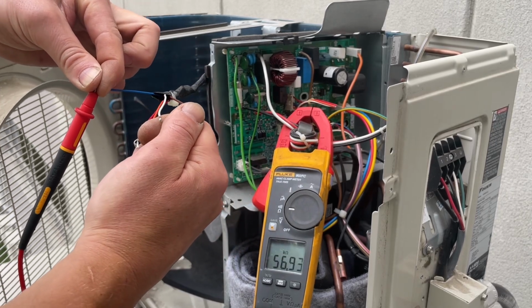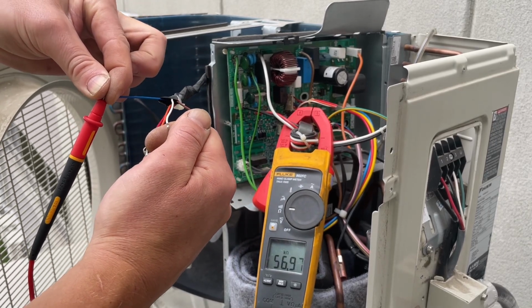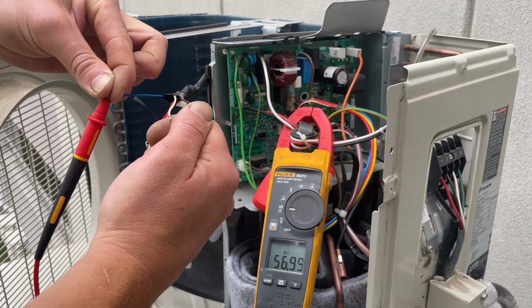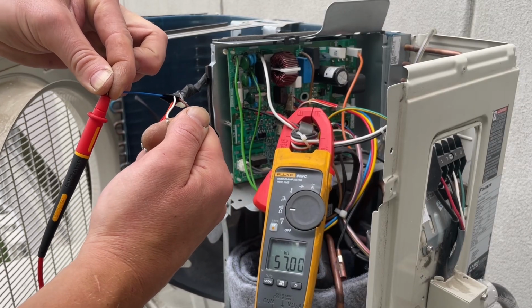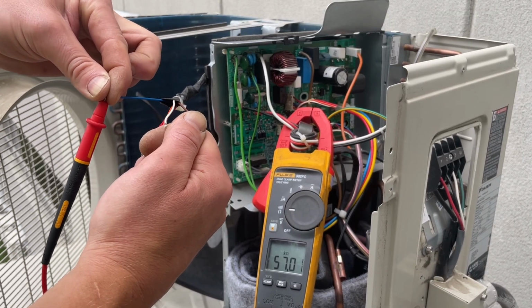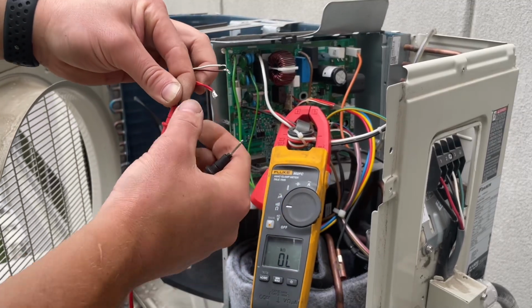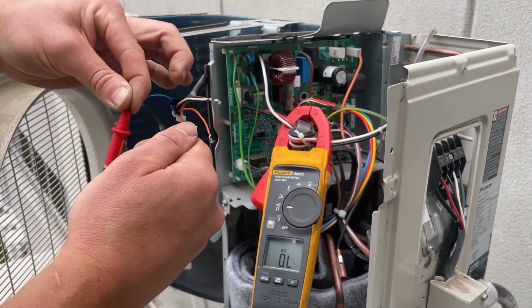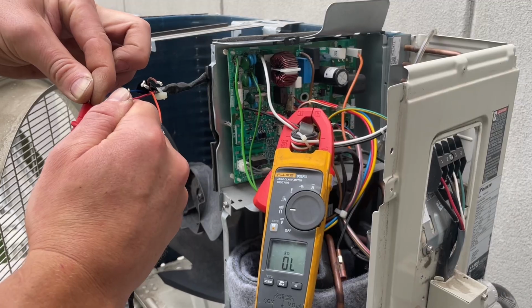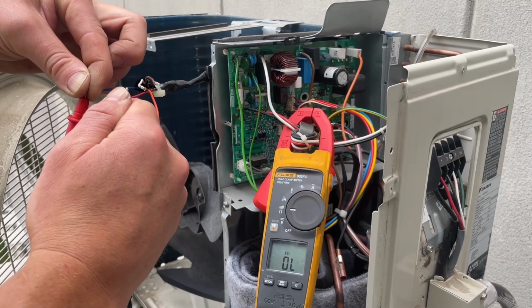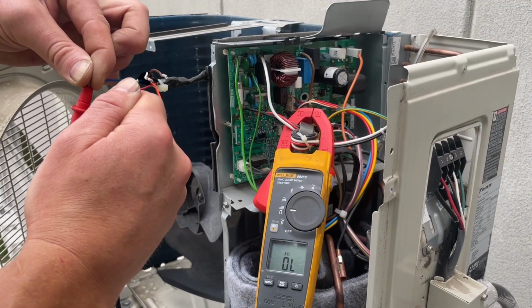which we have 56.94 kilo ohms. We're looking for 100 kilo ohms or more, or 100 ohms or more. I apologize. So this is no good. And then finally, our blue to red terminal here. We have out of limits, open windings. We're looking for 100 kilo ohms or more. So we know this condenser fan motor is dead.